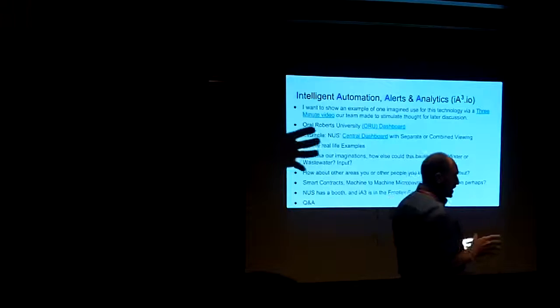Well, you picked up on the right point. The first thing is what protocols do the things you're choosing talk - that's probably the single most important thing. The second thing is, are they RS-485, are they Ethernet, or are they something else? Something else is unacceptable. It's got to be RS-485 or Ethernet, and Ethernet's probably preferred.